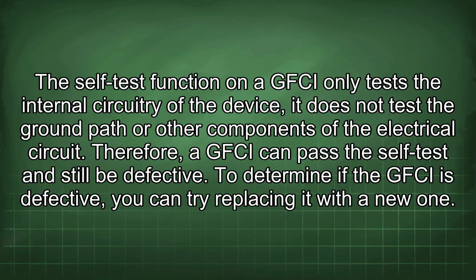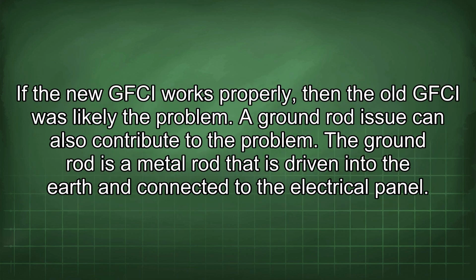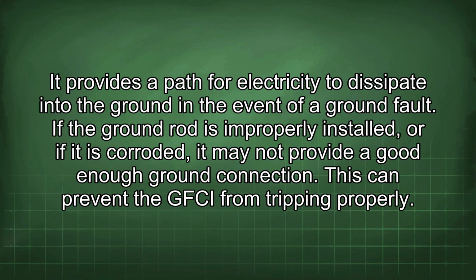To determine if the GFCI is defective, you can try replacing it with a new one. If the new GFCI works properly, then the old GFCI was likely the problem. A ground rod issue can also contribute to the problem. The ground rod is a metal rod that is driven into the earth and connected to the electrical panel. It provides a path for electricity to dissipate into the ground in the event of a ground fault. If the ground rod is improperly installed, or if it is corroded, it may not provide a good enough ground connection. This can prevent the GFCI from tripping properly.